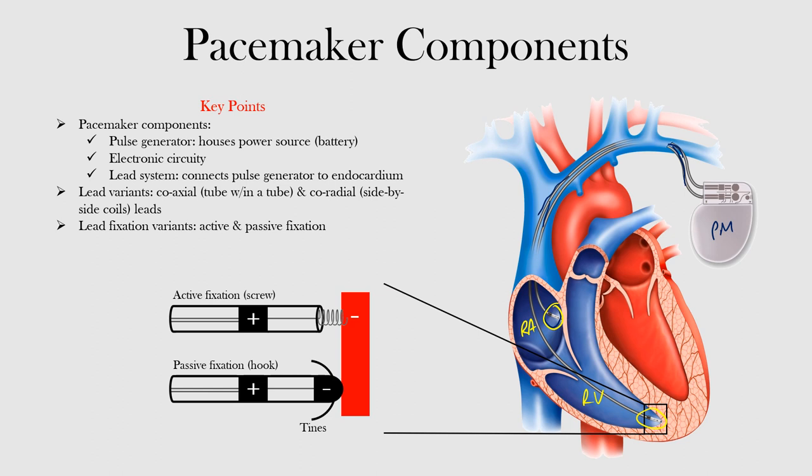These are the lead tips, and these leads can be co-radial or coaxial. The last thing to discuss is lead fixation, which is essentially how the lead interfaces with the myocardium. Lead fixation to the myocardium can be active or passive.